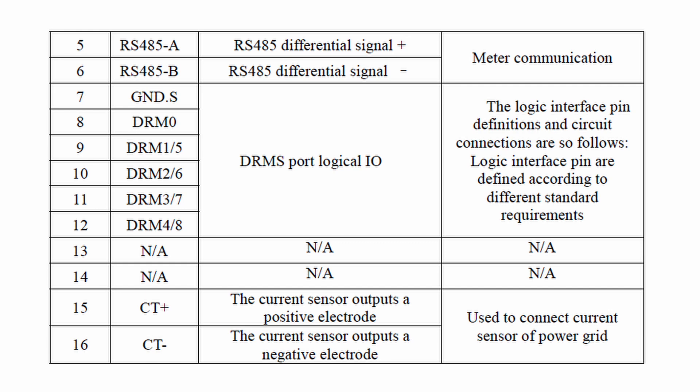First option is to use the CT only. Direct connection from the main incoming current transformer to the inverter is pins 15 and 16. Pin 15 is usually red which is positive, and either yellow or black on some CTs. With this option, you need to go to the inverter and choose in the PCC option 'PCC CT'. This is option number one for load monitoring with CT only, which works up to 30 meters between the inverter and the main incoming.